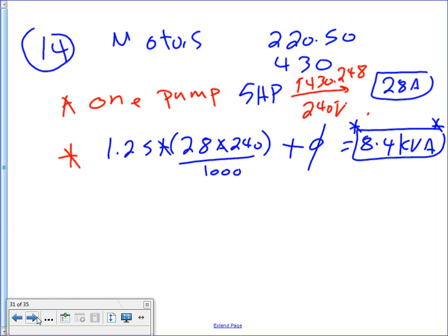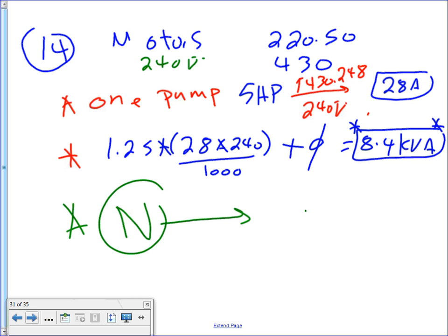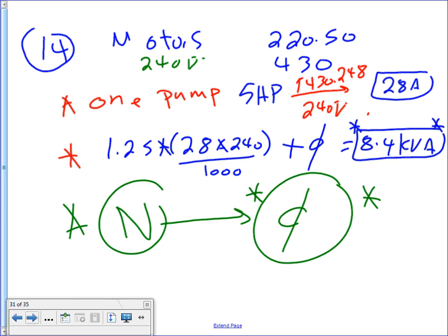So that's easy. Step number 12, the motors. For the motors, I want you guys to look at these motors running at 240 volt. Do you see any neutral with them? No. So when it comes to the neutral, you're going to put a big fat fluffy zero. Why? They're not running on the neutral. But I should write zero there. So I know when you do the math for me, guys, get into the habit when you size a neutral, put zero so you know it doesn't count.